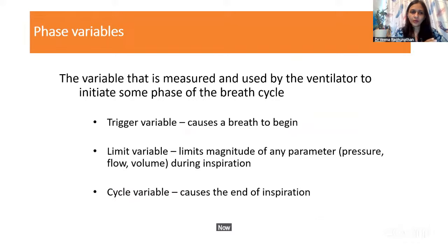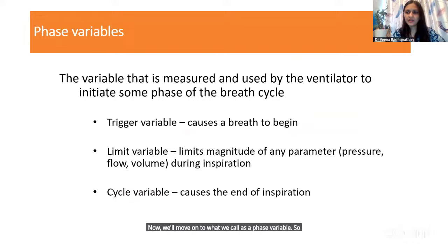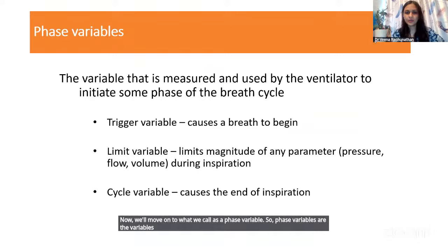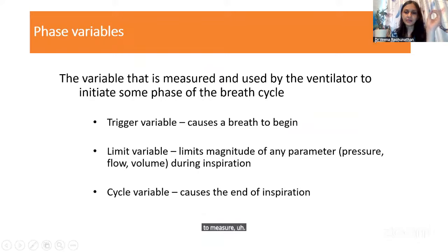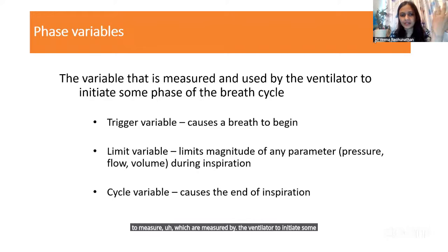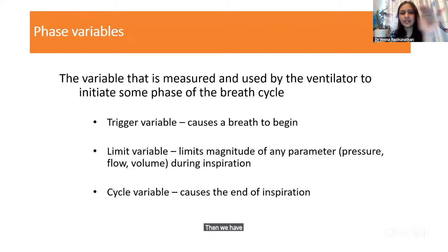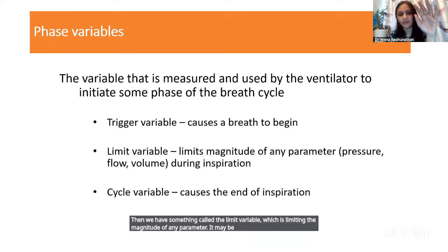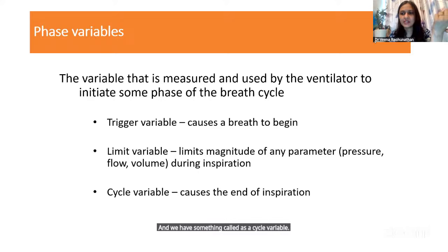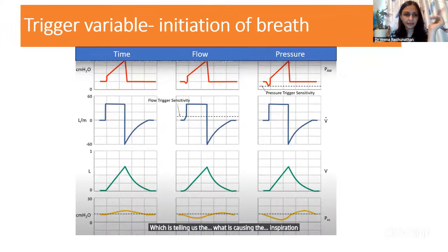Now we'll move on to what we call phase variables. The phase variables are the variables measured by the ventilator to initiate some phase of the breath cycle. So we have a trigger variable, which is the reason why the breath begins. Then we have the limit variable, which is limiting the magnitude of a parameter. It may be pressure, it may be volume during the inspiration. And we have the cycle variable, which tells us what is causing the inspiration to end.